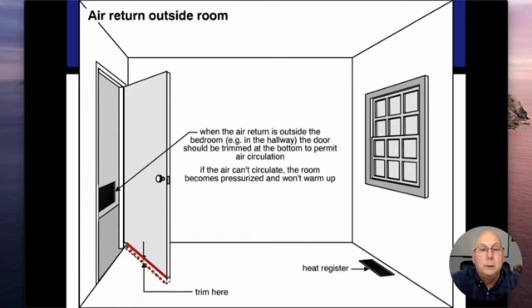We also need to make sure that the air can flow in and out of that room with ease, not only when the door is open, but when the door is closed. These things are designed to have an undercut under that door, so that as I'm blowing air in, I can let the air get out. If I have carpeting or that opening's too small, that's going to restrict the amount of airflow coming out of there. I've seen where they'll put grills up in the ceiling as well. I think that's a great idea, something that permanently lets it get out of there.